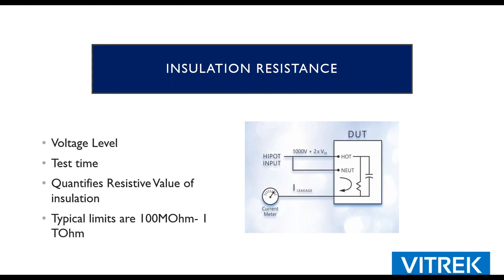So we're actually going to make that measurement, convert the current into ohms simply via Ohm's law, and we're going to represent the value of that insulation. It could be 100 megohms, it could be 100 gigohms. You're able to set limits around that. 100 megohm is a very common requirement, but at the end of the day, instead of measuring the current that's flowing between the two conductors, we're going to quantify the value of the insulation, and that's what an IR test does.